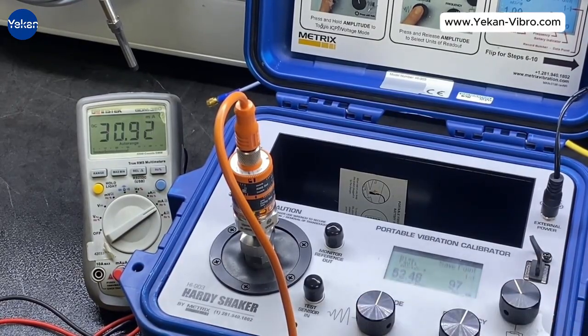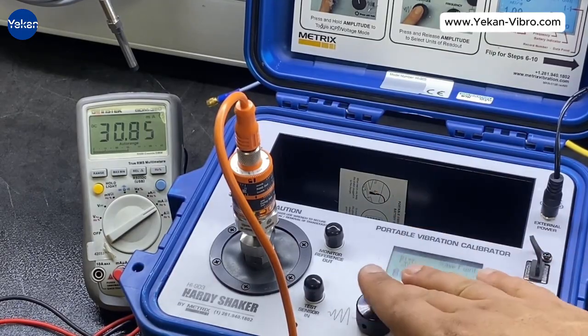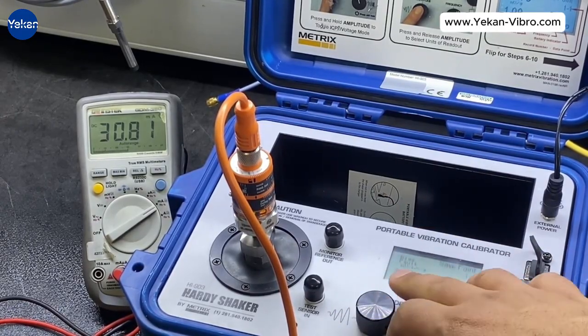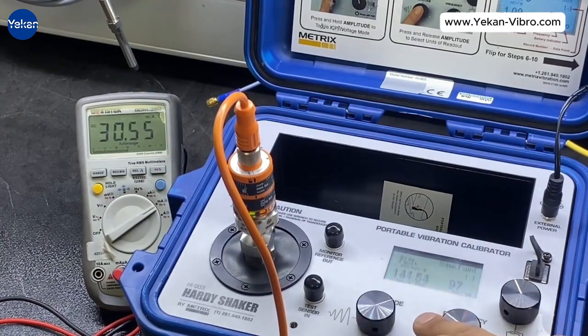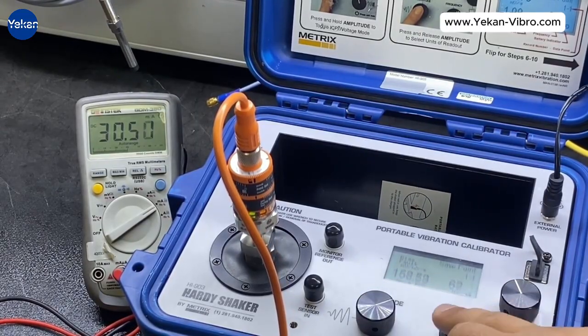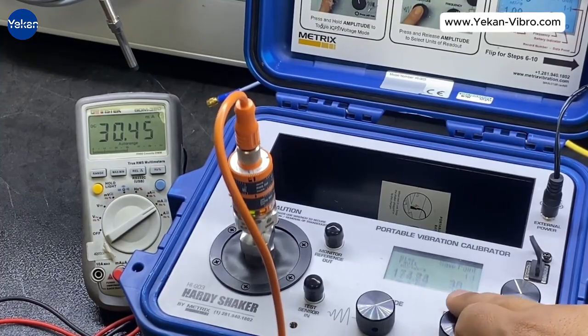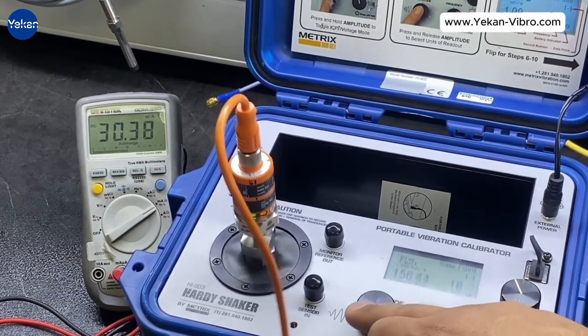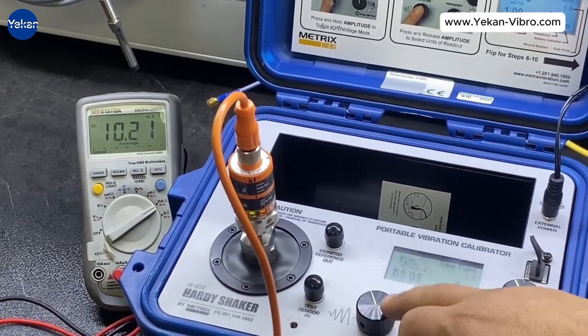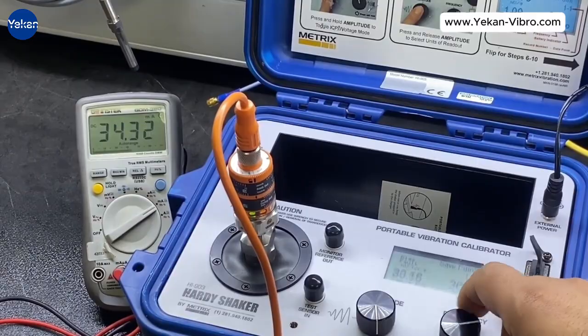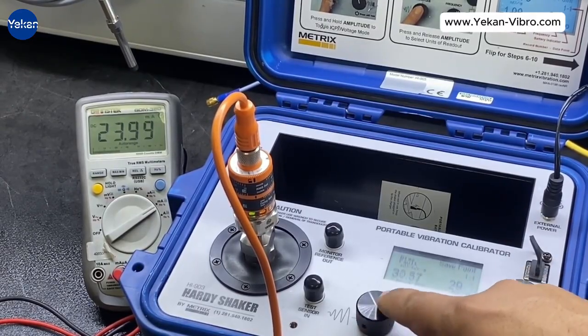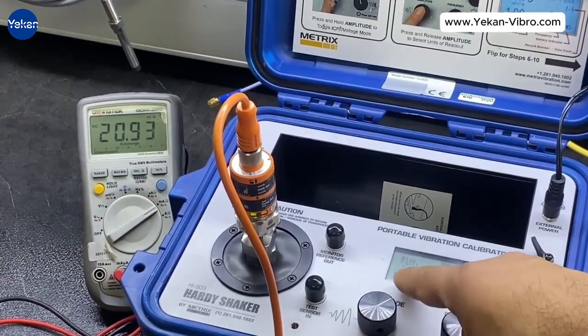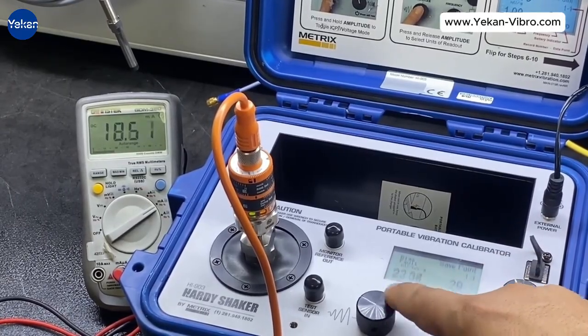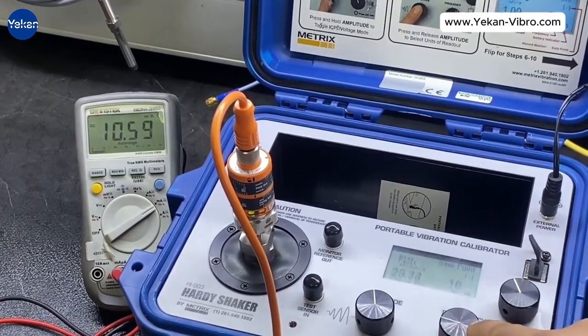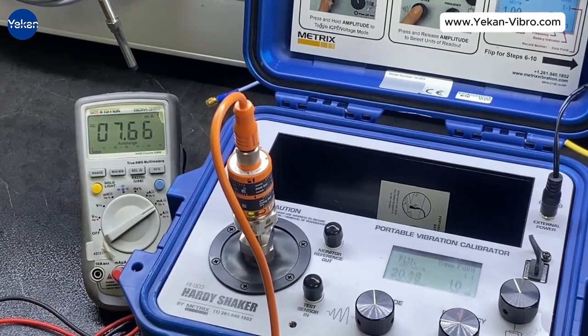Piezoelectric sensors usually stop at 20 milliamps to avoid overflow. But here, the current keeps rising as vibration increases. I now set the frequency to 10 Hz. Note that the sensor is labeled to work from 10 to 1000 Hz. Let's test it. I set the amplitude to 20 millimeters per second. At 10 Hz, the output is only 7.6 milliamps.